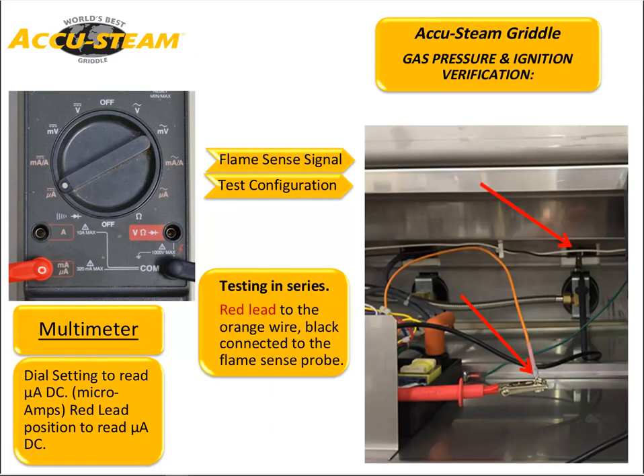If we move forwards, here we have the griddle, and again, we're going to be using DC microamps. The hookup is slightly different. We have an orange wire that connects to the flame sensor here. You will remove that orange wire, connect your positive probe to the orange wire and your negative to the rod, the flame sense rod, in series. The griddle will still work during this hookup.